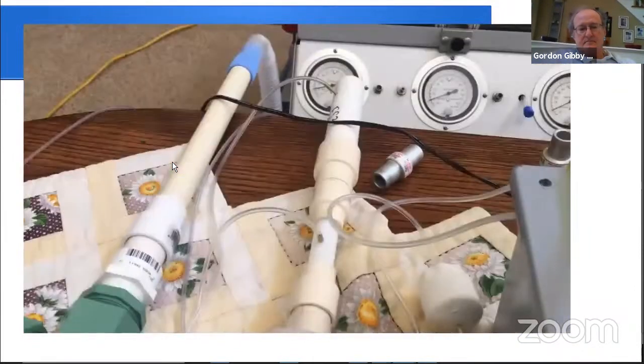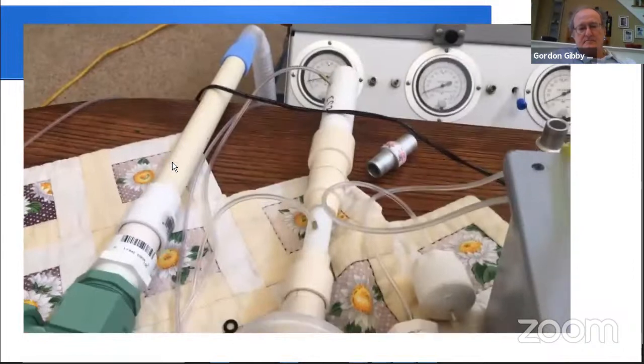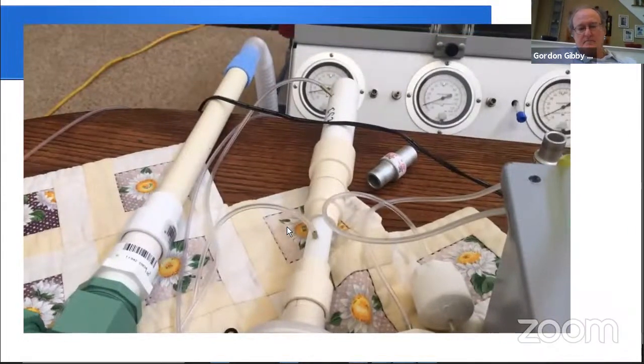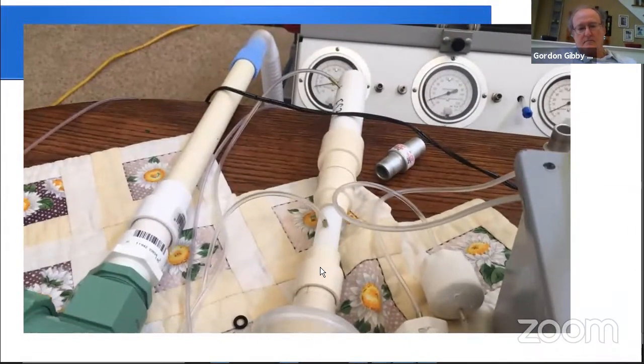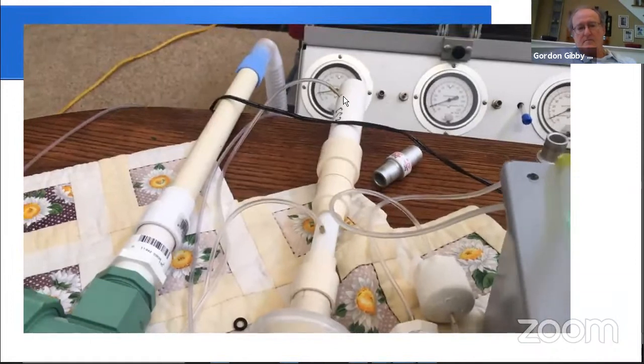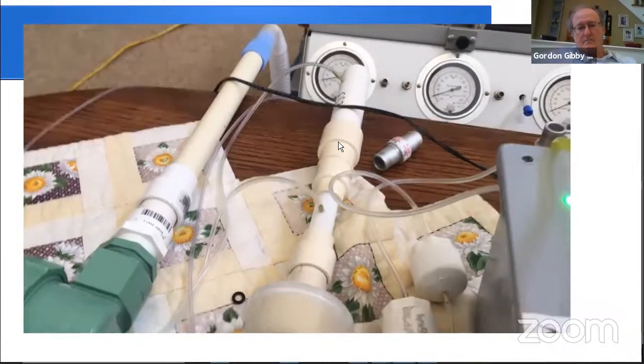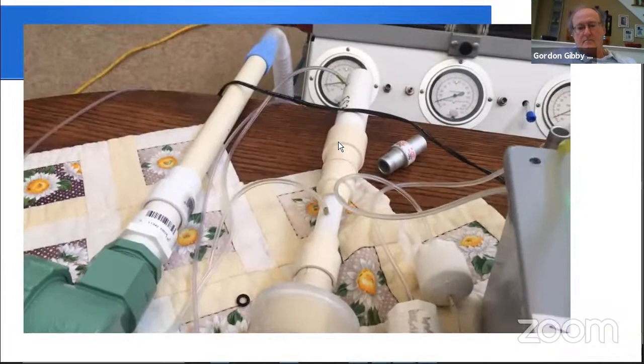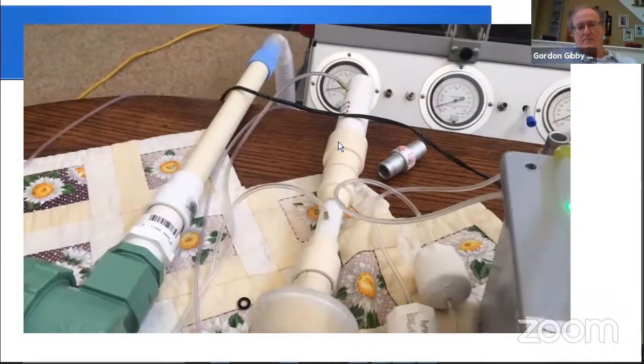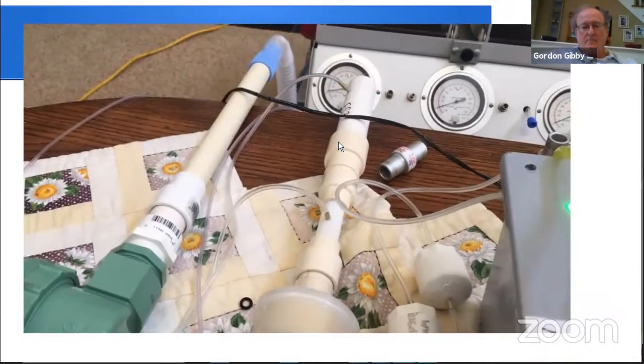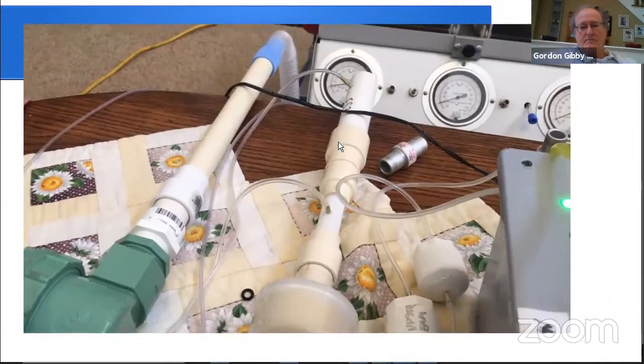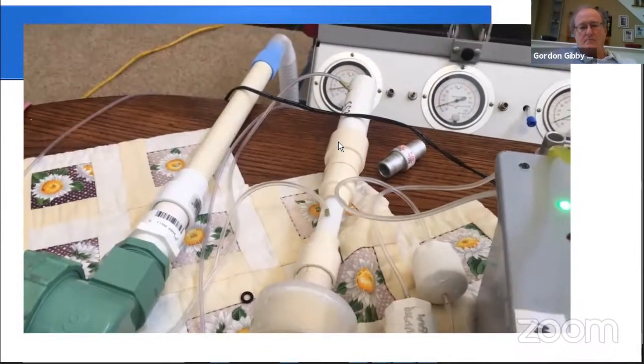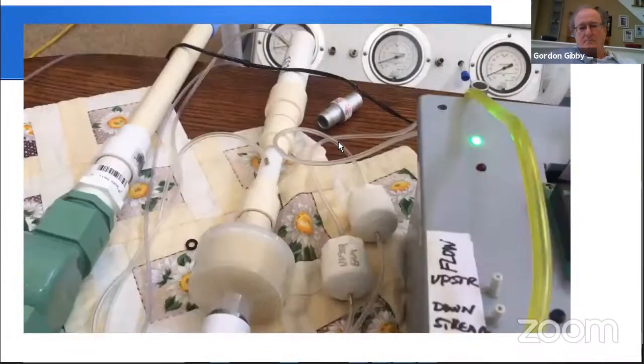This is a homemade Venturi. It has an obstruction in it, and we measure the pressure up and down from that obstruction, and then it's just Ohm's law. By knowing the pressure drop and knowing the resistance to that obstruction, we're able to calculate instant by instant the actual gas flow in liters per minute, and it's astonishingly accurate. I could not believe we did that.